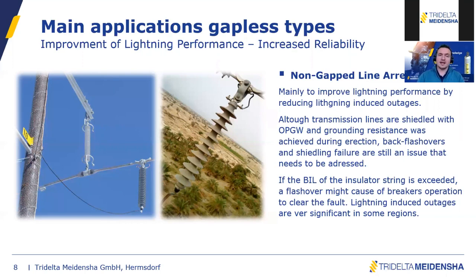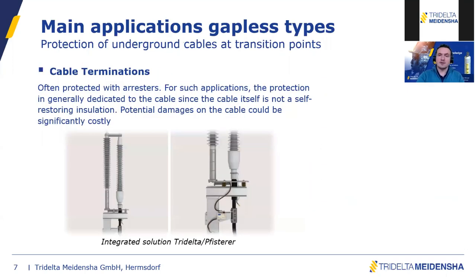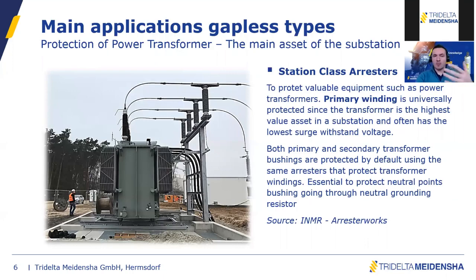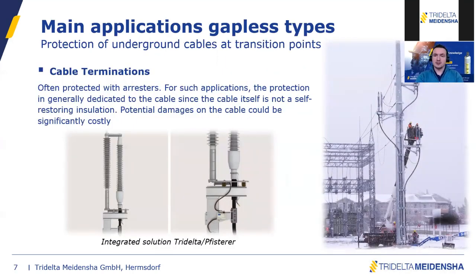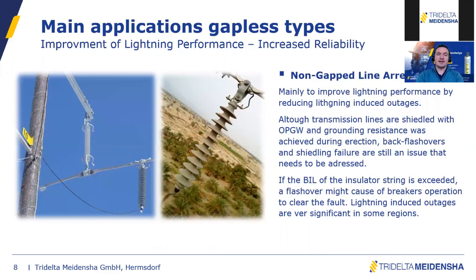So it is important to make a distinction between these three applications. If I summarize quickly, we have a very common application to protect valuable assets in your substation. It's kind of mandatory because the transformer is extremely expensive. Then we have a cable termination to protect the cable itself, because this is a sensitive transition point where you don't want the cable insulation to be damaged, which is also associated with significant cost. And then for the line arresters, you don't want to protect the insulators. Actually, you want to prevent a breaker operation. You want to prevent a lightning-induced outage. So this is one gapless type for three different purposes.